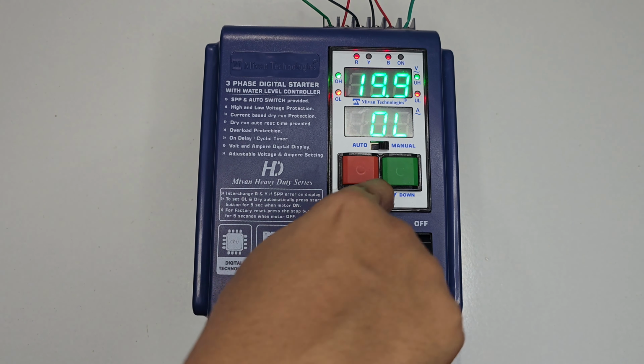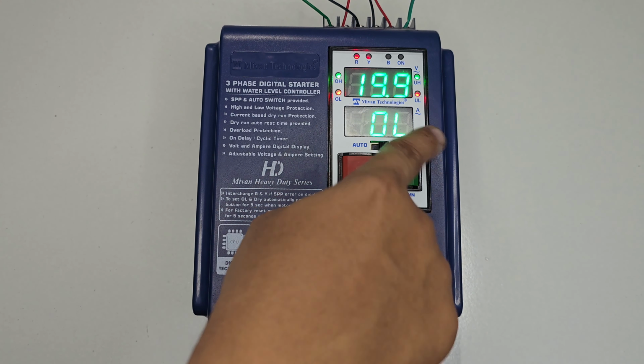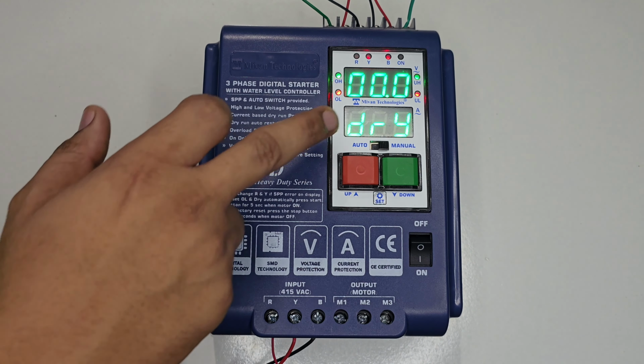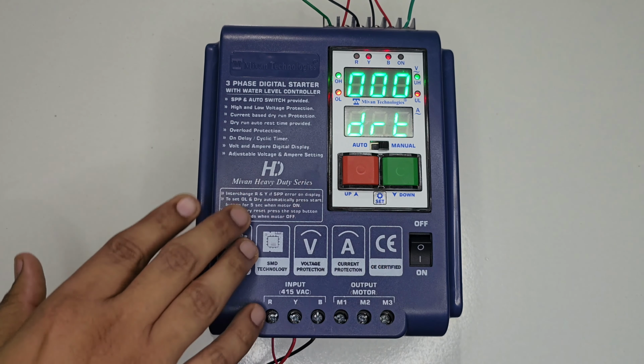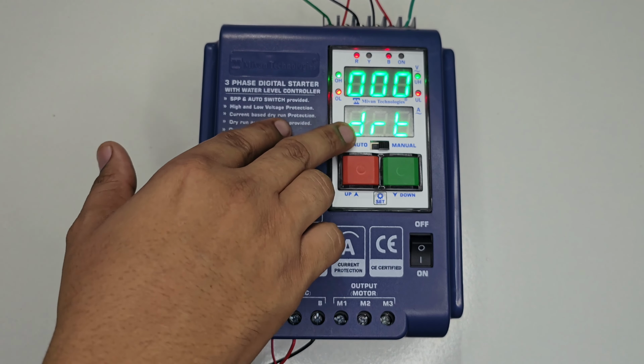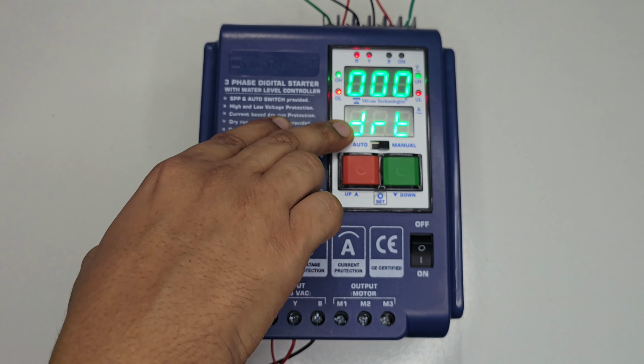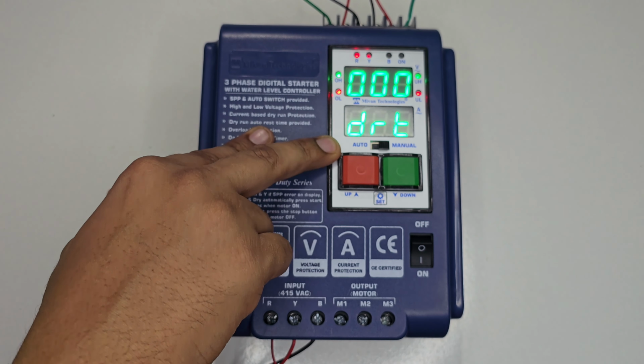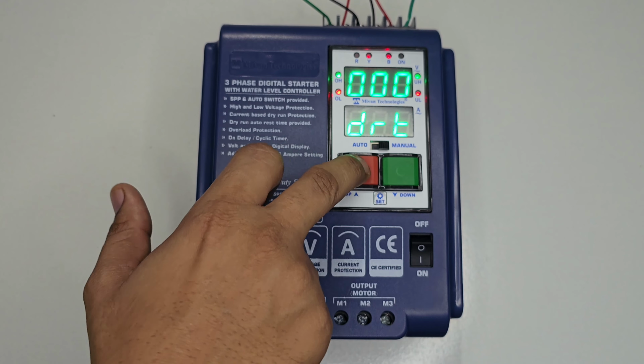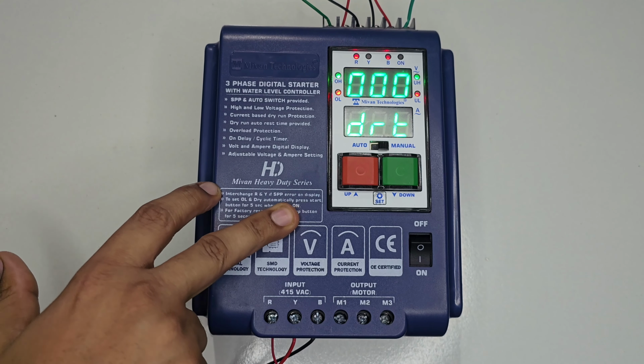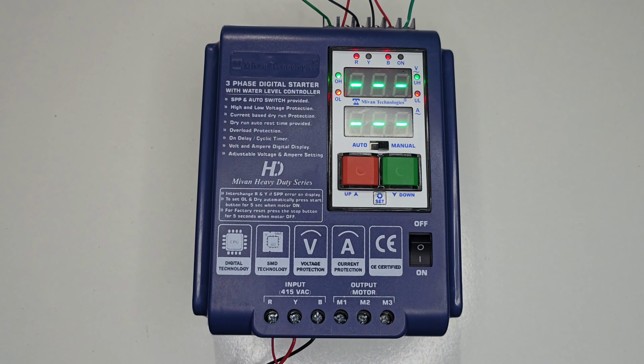In the main menu, press the set button, the overload comes. Press the set button, dry run comes. Press the set button. Here you can see a dry run reset timing option. You can set the dry run reset time in minutes by pressing the up and down key. Press the set button and it comes to the main menu.